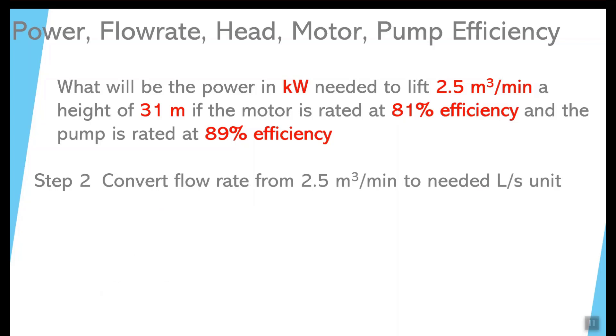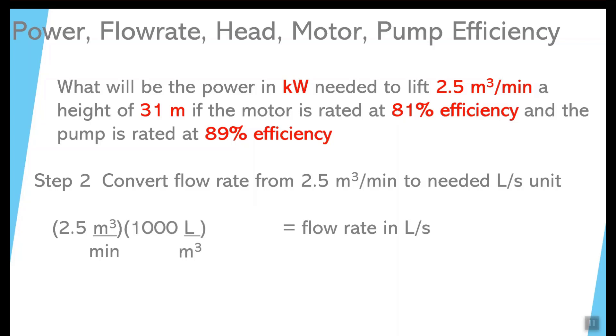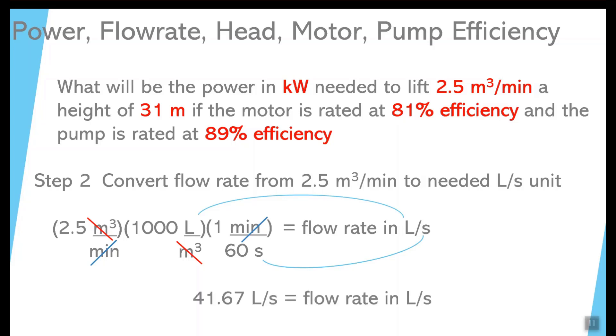Before we can plug all those numbers into the big formula, we have to do a conversion from cubic meters per minute to liters per second. First, convert cubic meters to liters by multiplying by 1,000 — the cubic meters cancel out, giving 2,500 liters per minute. Then divide by 60 because there are 60 seconds in one minute. The units cancel out, leaving liters on top and seconds on the bottom, giving approximately 41.67 liters per second.